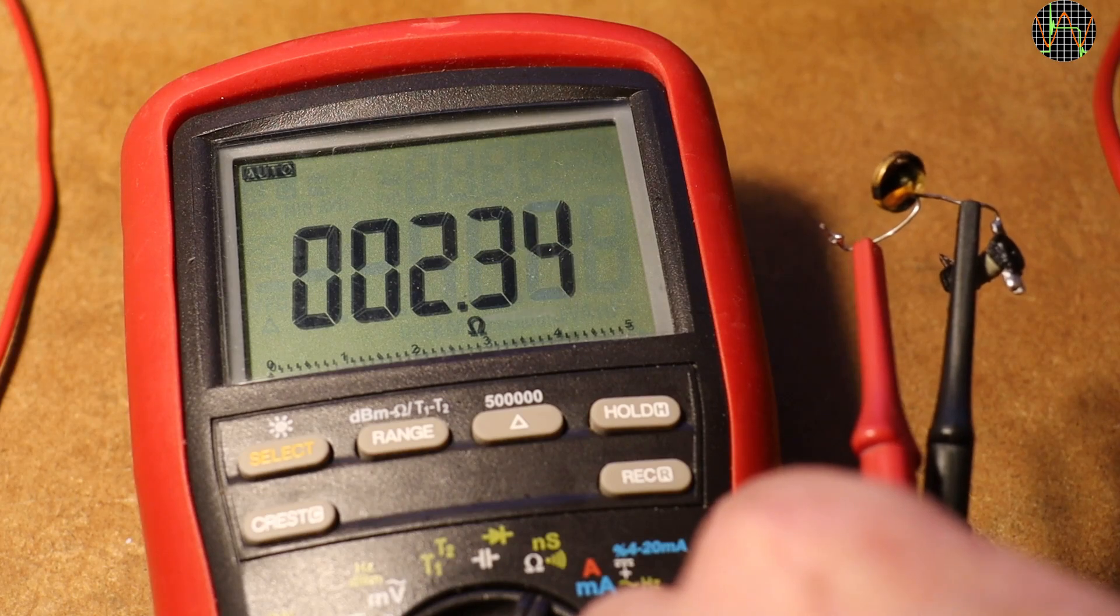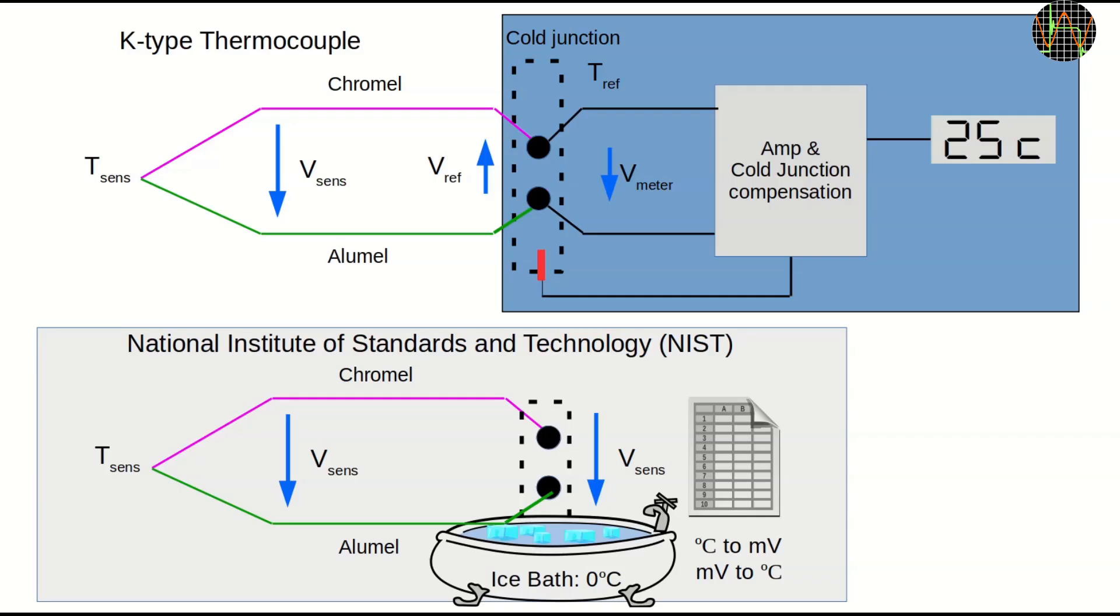So that is the cold junction compensation. I have covered thermocouples before, but let me briefly explain cold junctions using a K-type thermocouple. A J-type works just the same. The junction of two different metals produces a tiny voltage through what is called the Seebeck effect. The hotter the junction is, the more voltage. This is what a thermocouple is. A junction of two dissimilar metals.